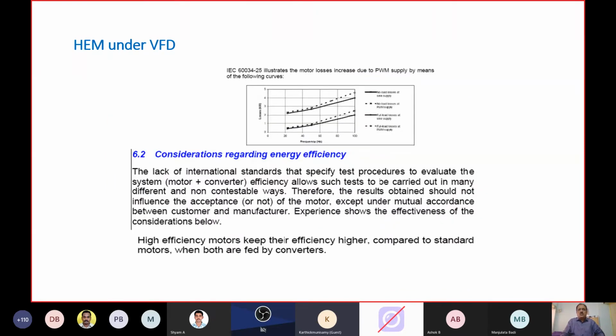So, high efficiency motors: some people will have doubts whether I have to necessarily buy an IE3 with a VFD, why I should not buy an IE2, since anyway there is an additional loss in the motor. This one slide here, as illustrated by 60034-25, clearly states that the higher the efficiency, the more the motor efficiency is retained with the VFD also, and therefore it's always prudent to use higher efficiency motors, IE3 or IE4.